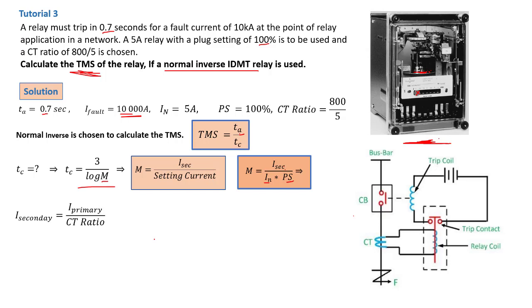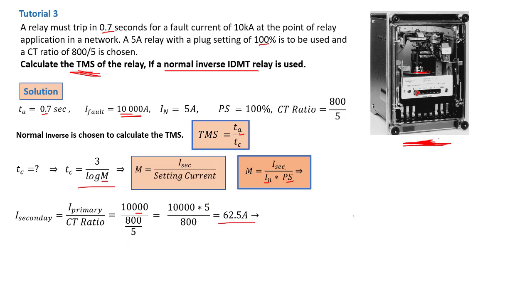We calculate the secondary current by replacing the primary current with 10,000 amps and dividing by the CT ratio of 800/5. This gives a secondary current of 62.5 amps. Then m = 62.5 / (5 × 1), where 5 is the nominal current and 1 represents the 100 percent plug setting. That gives us m = 12.5.